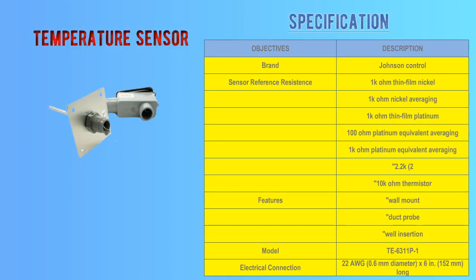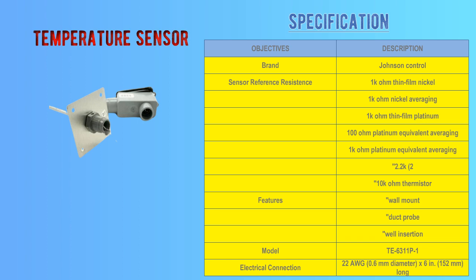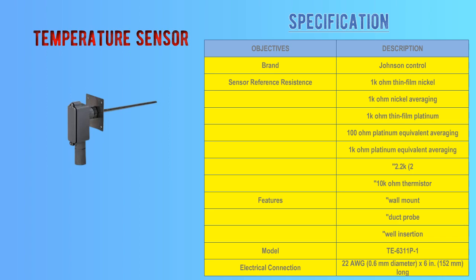Now take a look at some of the field devices which are commonly used in any project, such as a temperature sensor. On the right side you can see the specifications of the field device. This is a product of Johnson Controls — an air temperature sensor. It is used for sensing the temperature inside the duct, outside temperature, and it can also be wall-mounted. There are many types of sensor resistance available in the market such as nickel, platinum, thermistor, and NTC. 22 AWG wire is acceptable as per standard protocol.